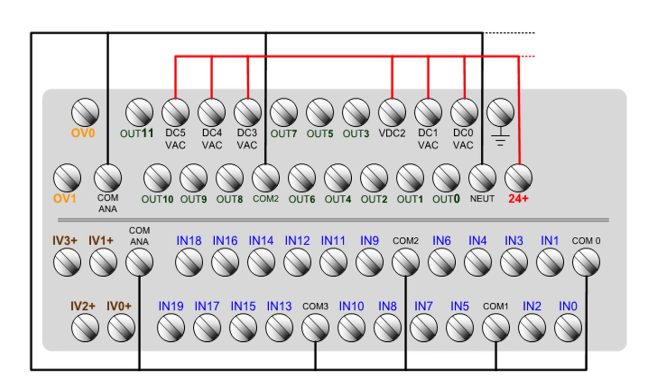Or if I want to use a different voltage, I just remove the jumper and rewire it to the next point, leaving, let's say, DC 4. I want output 9 at AC. Well, I just disconnect DC 4 from the daisy chain between 3 and 5, and then I wire up my AC to DC 4 and output 9 through the output device, the load.